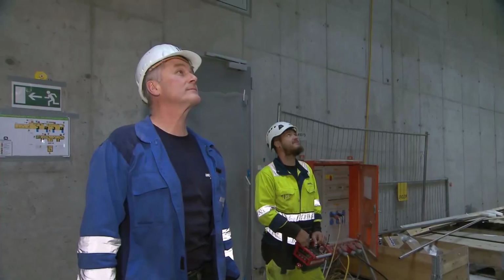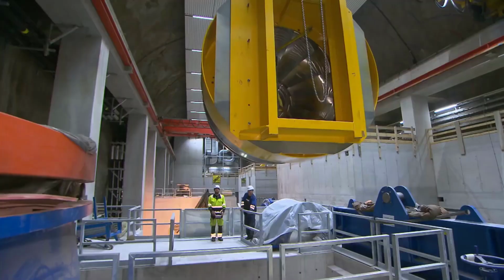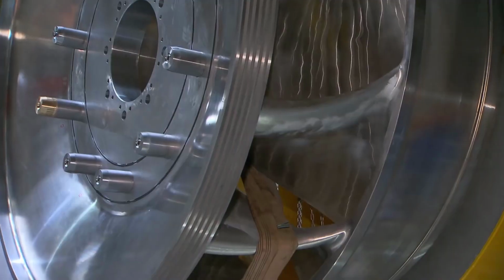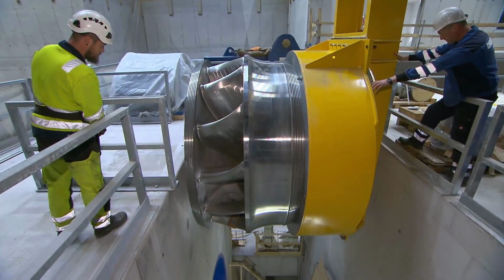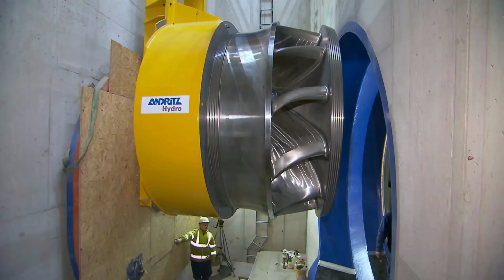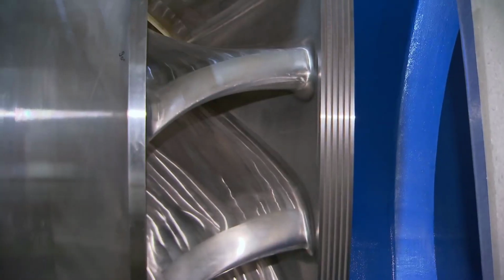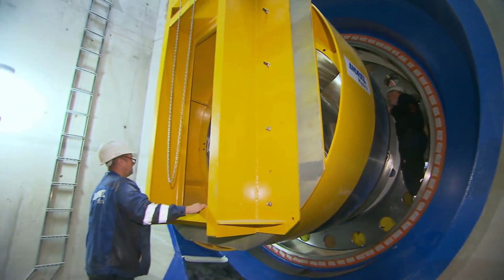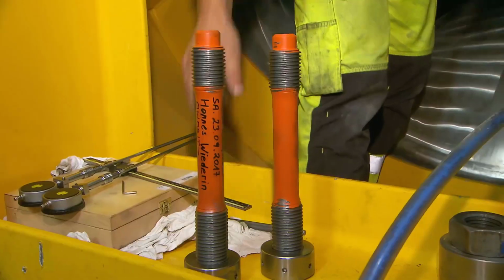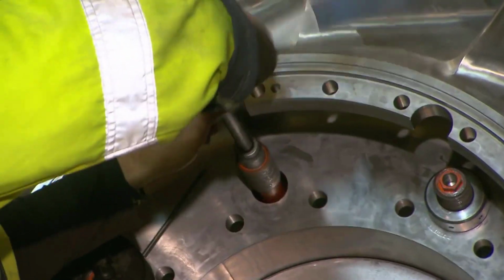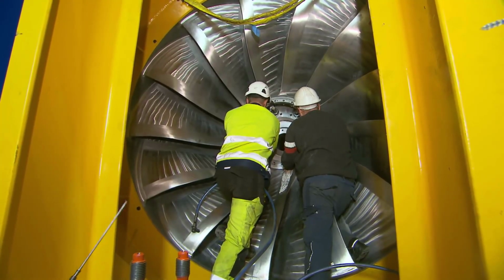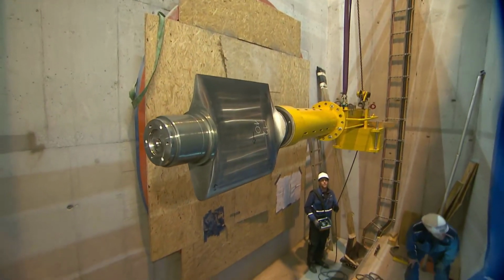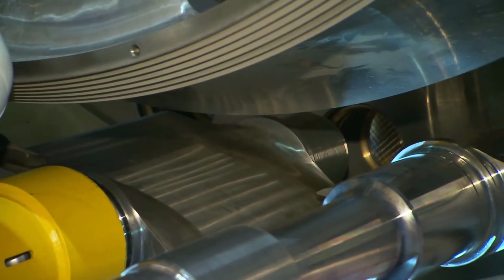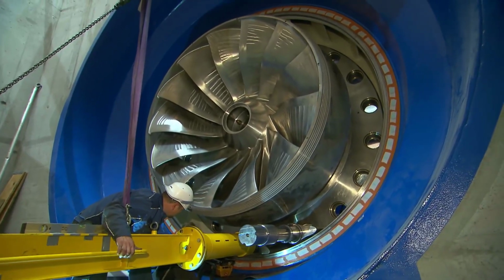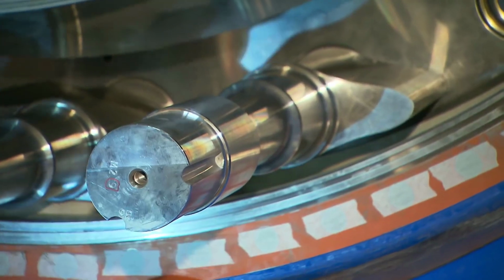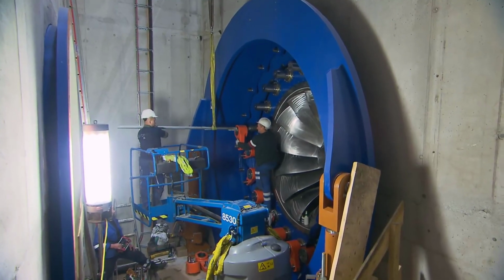Intensive work is being carried out on both machines, with all components gradually arriving. The Francis turbine runner is being installed, and due to limited space between the individual parts, the assembly poses a special challenge for the technicians. An assembly facility specially designed for this construction site is used to precisely fit and screw the components. It won't be long until the runner turns for the first time, marking another step towards the completion of the turbine. The installation of the guide vanes, manufactured in Ravensburg, is another crucial step. The 20 guide vanes will control the water flow on the runner, regulating the power. They are bolted and connected to the control mechanism.